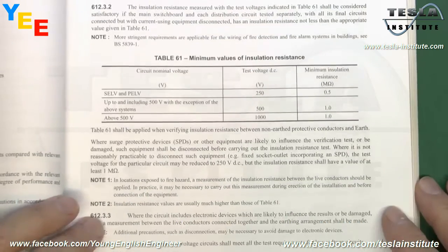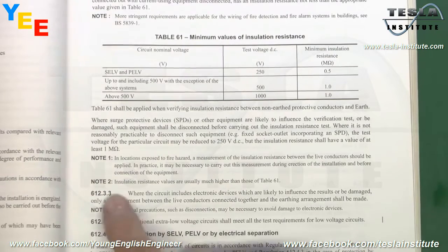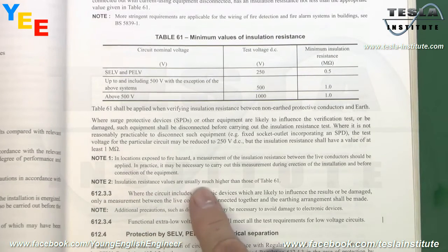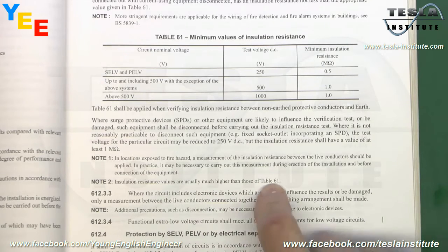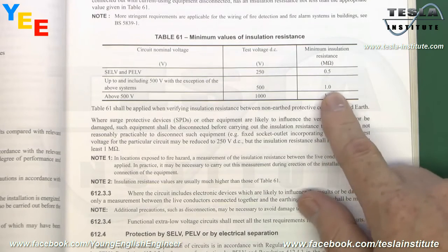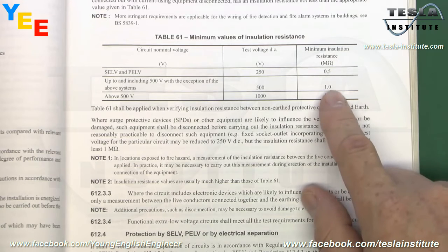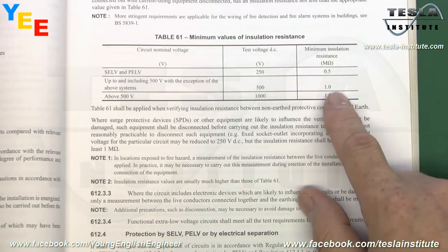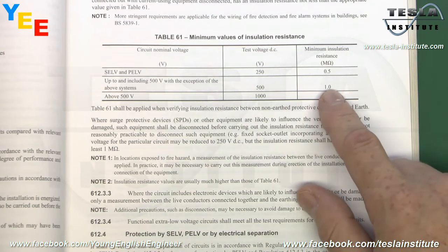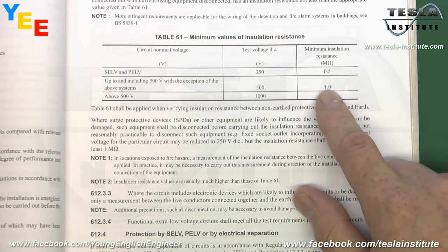And before we put this book away, there's just one thing here to take note of, which is this Note 2. And it says here, insulation resistance values are usually much higher than those of Table 61. So though this 1 megohm is actually the minimum, in reality you want to be seeing values much higher than this. And so certainly for a new installation you want to see values in the hundreds of megohms.